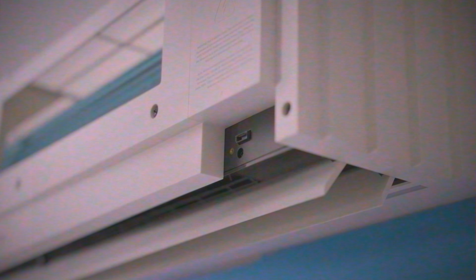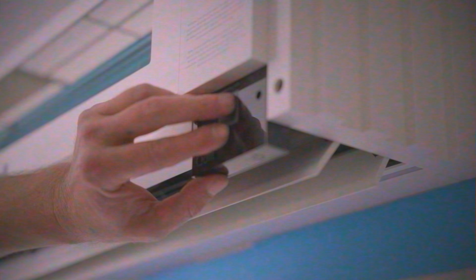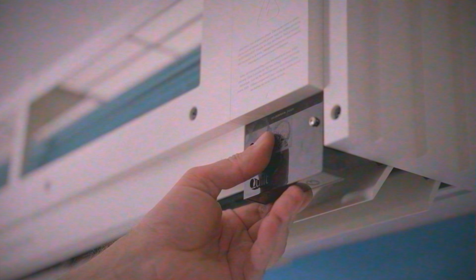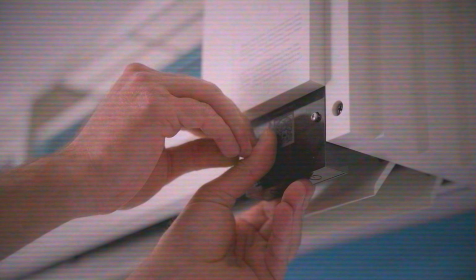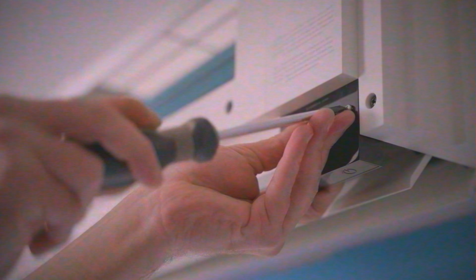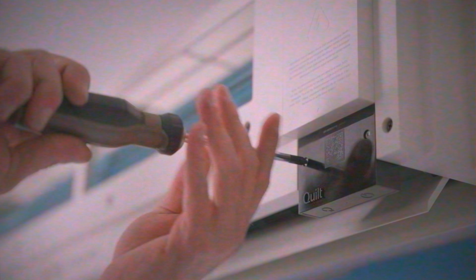The Quilt Sense module gets reinserted next. Each Quilt Sense module is assigned to a specific room, so make sure you're installing the correct one for this unit. Carefully insert the module. Once the magnets engage, the module should sit flush. Then use a screwdriver to hand tighten the 2 M3 screws.